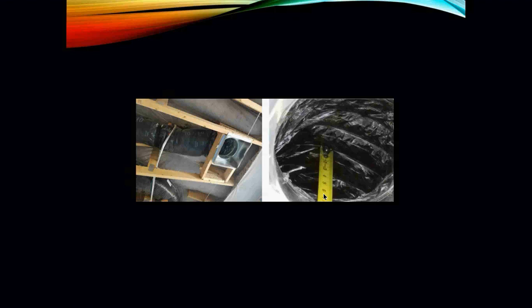So to fix this particular type of issue, instead of running the flex duct like they did and making a connection here, they should have put a 45 or a 90-degree elbow right up in here and made the connection out here with the flexible duct, so that when that connection is made, it is still maintaining a 10-inch round all the way through and out into that supply.